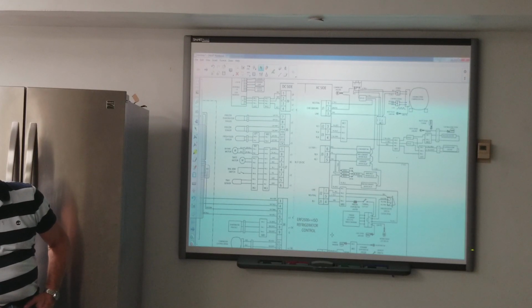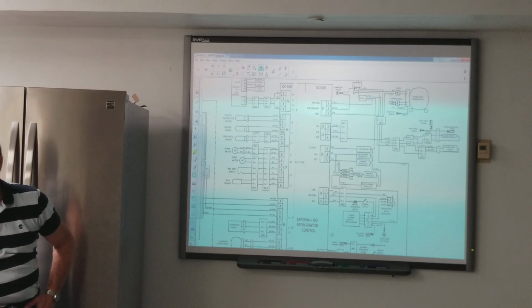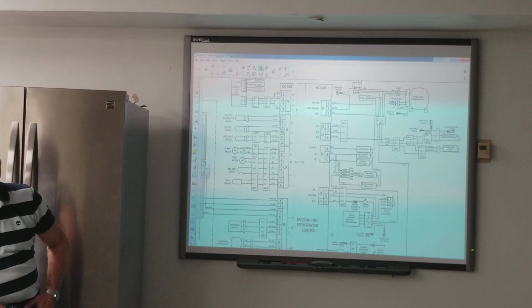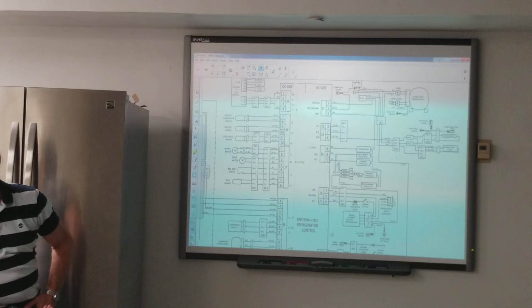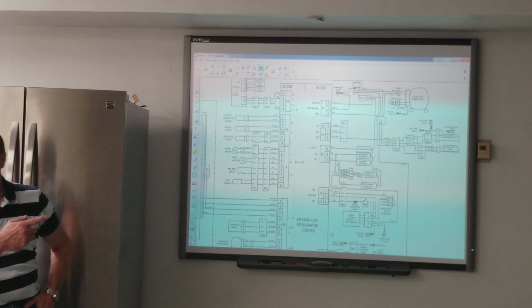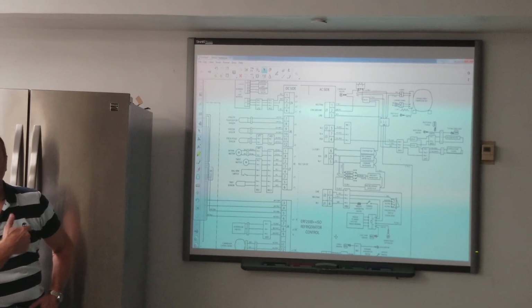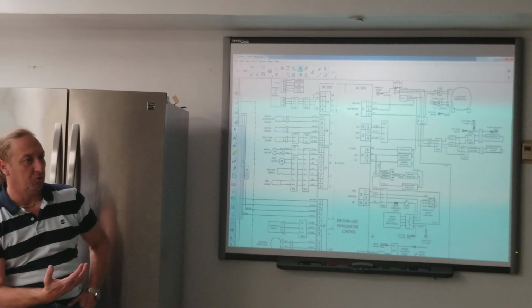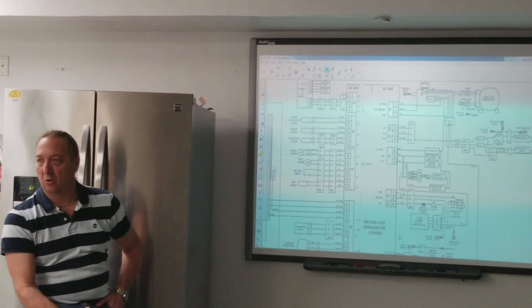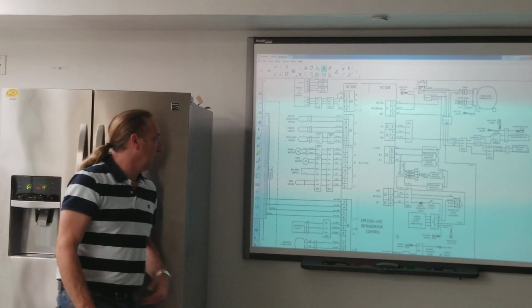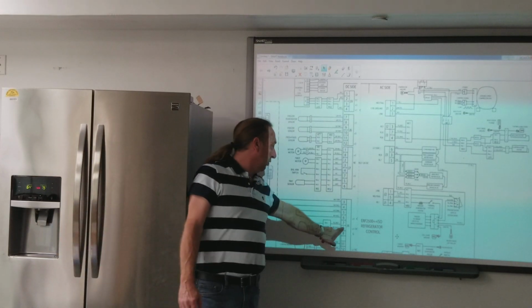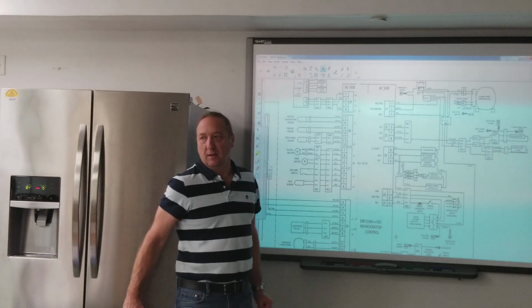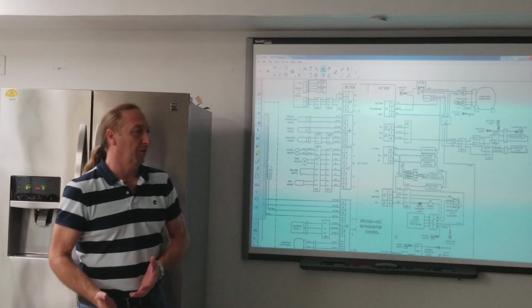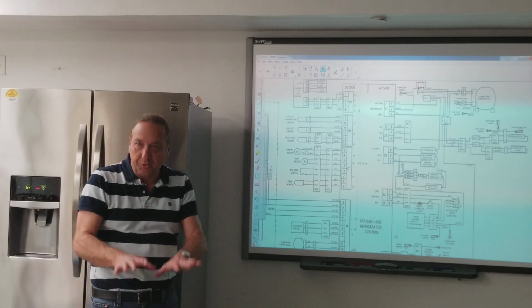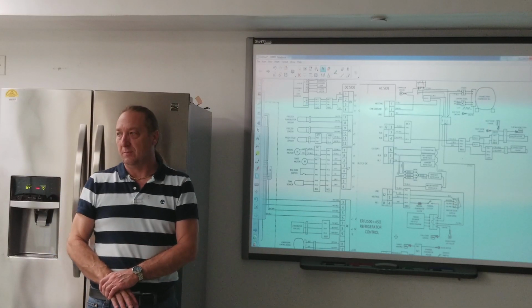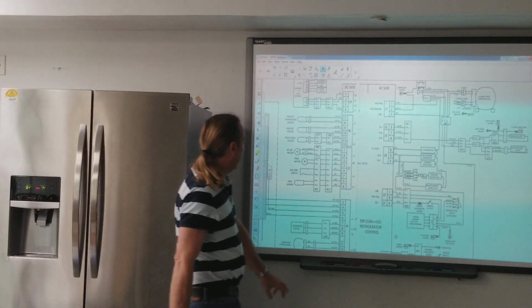The board is using that third wire to know how fast the fan is running. There's a sensor built into the fan, so the communication between the fan and the board lets it know if the fan's running fast or slow, and to speed it up or lower it. That's controlled by the voltage on pins 8 and 9. If I raise the voltage, the fan runs faster. If I lower the voltage, the fan runs slower. So that's what that plug is for.